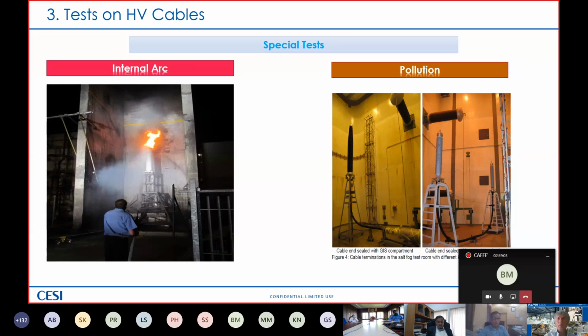And that is also the main reason why utilities want to have this test being performed, to be sure that there is a so-called explosion-proof solution, because in case of an urban high voltage substation where you have a porcelain cable termination, it's a must to avoid this kind of explosion in order to save life and to reduce the danger to all other equipment in the substation. This is the main reason.